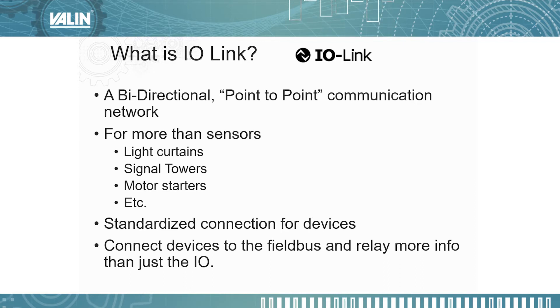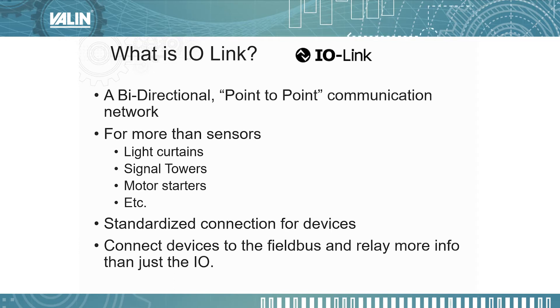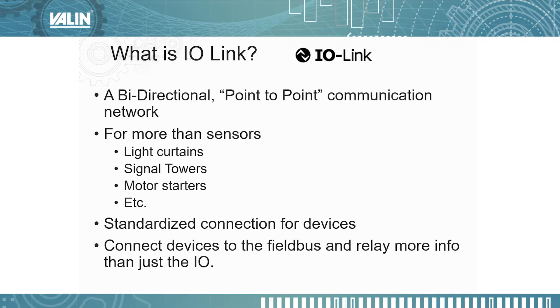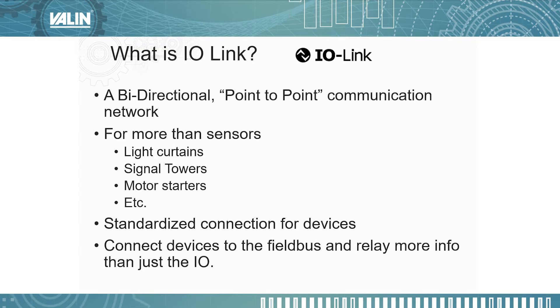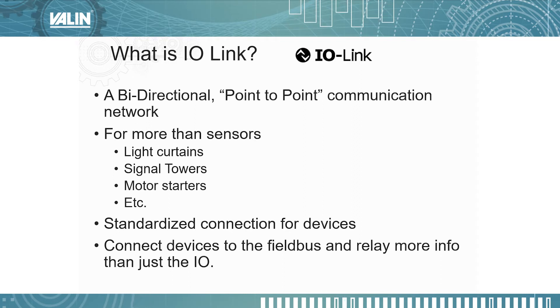It's a standardized connection for devices, so your device will have either three or four wires and will connect to three or four connection points on the IO-Link master — whether it's a light curtain, a signal tower, or a sensor. The devices connect to the IO-Link master, and then the IO-Link master connects to the upstream main controller. You might think this sounds just like wiring a sensor to an input module, but the difference is that with IO-Link you get more than just the digital IO info.